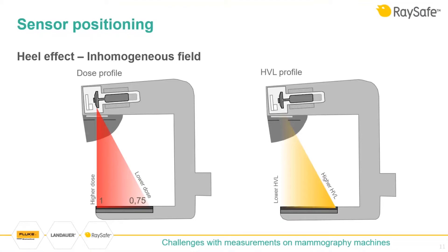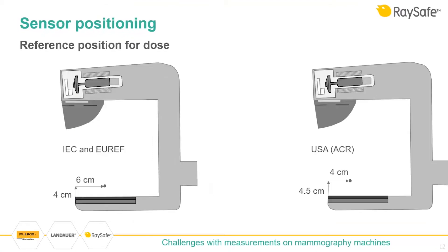You have the same but opposite effect for HVL. The reference position for dose varies around the world. EUREF says that dose position should be at 6 centimeters from the chest wall side and 4 centimeters up from the examination table, while in the US, MQSA says you measure 4 centimeters from the chest wall side at 4.5 centimeters height. Dose measured at a different height can be recalculated using the inverse square law, but the distance from the chest wall side has to be at the reference distance — it's not easy to recalculate afterwards.